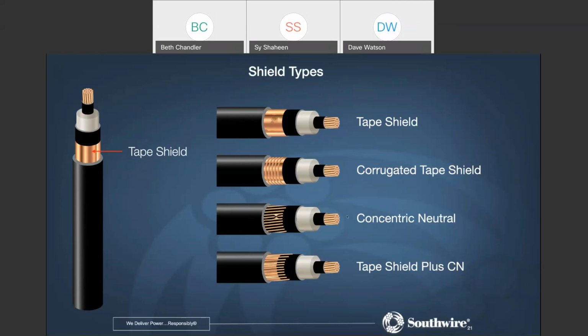Now this one looks like one conductor, but in reality it's two conductors, because this is the phase conductor and this is the neutral, and hence the word concentric neutral. This one is designed so it can handle neutral returns, and that's usually mostly used in utilities. In utilities there's a lot of imbalance between the phases, phase A, B, and C, because each phase is feeding a different subdivision. And once you get into a subdivision, you have so much diversity in loads and in use of loads, so that phase A might carry more current than phase B or C, because not everybody's turning on their air conditioning at the same time, or the welders, or their power equipment, or the coffee makers, or the TVs, or the hair dryers. That's why a concentric neutral is used to return that current.